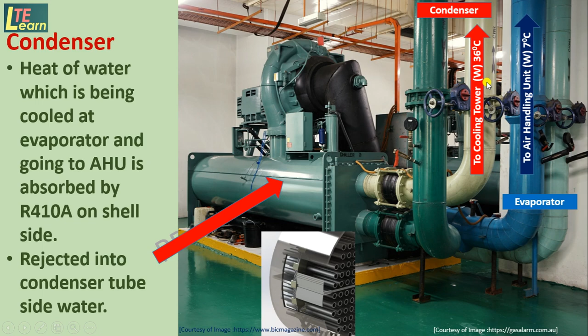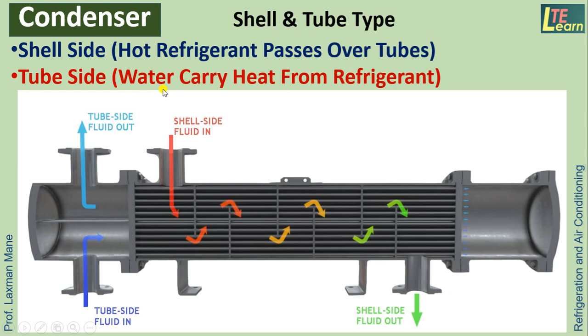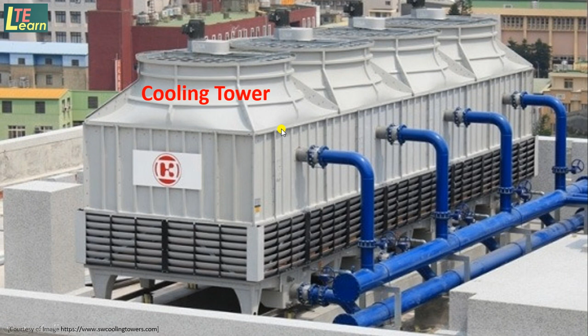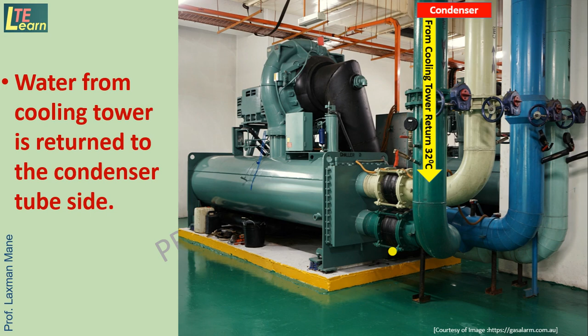Here the condenser is of shell and tube type, in which hot refrigerant is carried on the shell side. So hot refrigerant passes over the tubes, and the tubes carry water, that is cooling water. The water line from the condenser, that is the warm water line, comes to the cooling tower unit for heat rejection. This hot water is allowed to fall down, where it comes in contact with air which is forced in an upward direction. So here heat exchange takes place between the air and water. Thus this air gets warm and heat is rejected to the atmospheric air. In turn, water is cooled. This cooled water returns to the condenser at 32 degrees Celsius. So water from the cooling tower is returned to the condenser tube side.